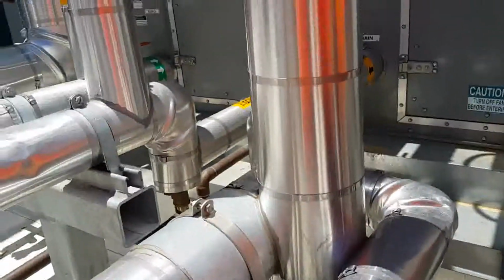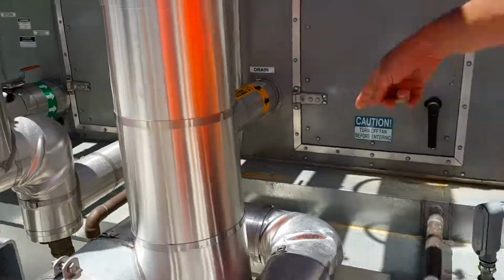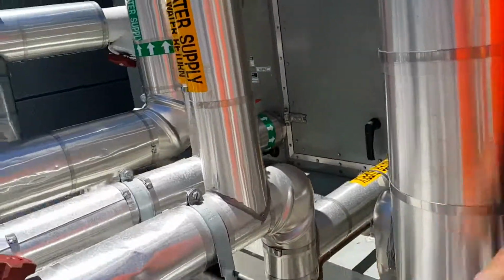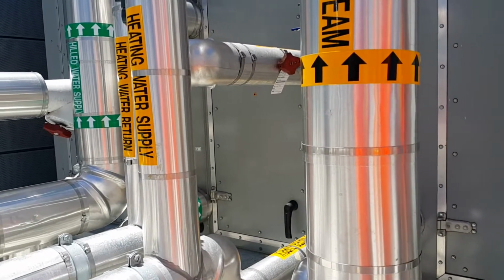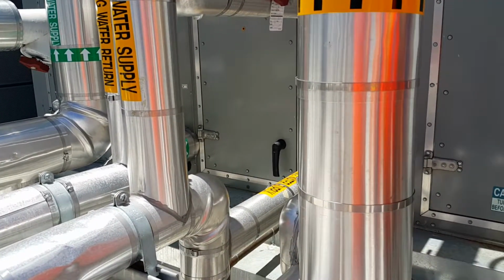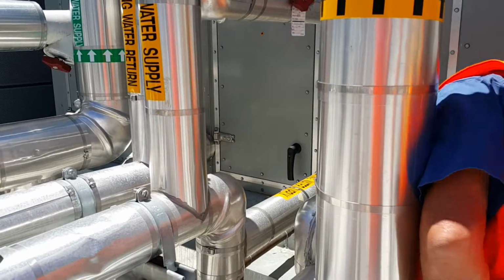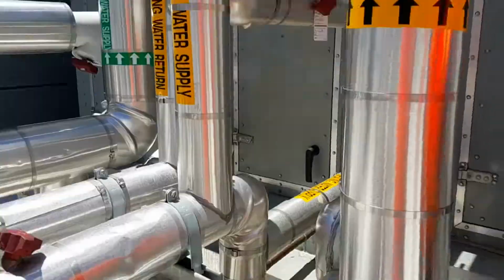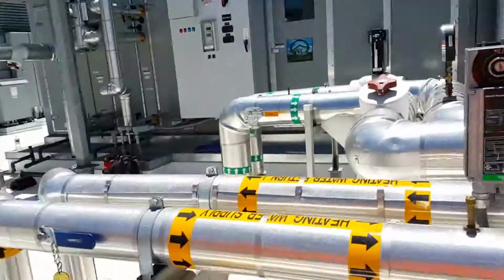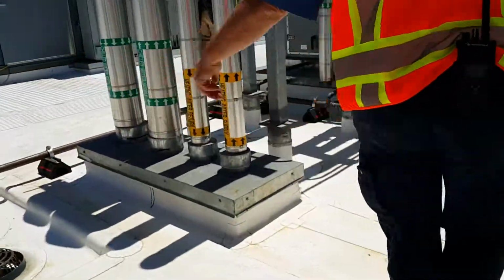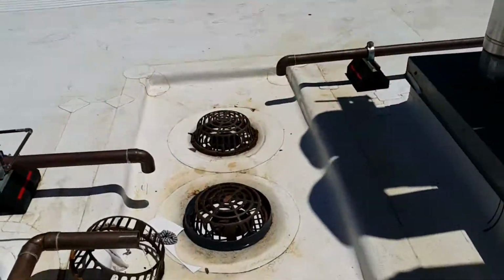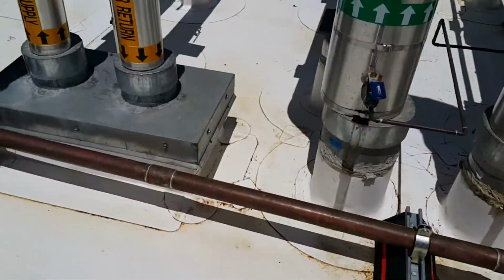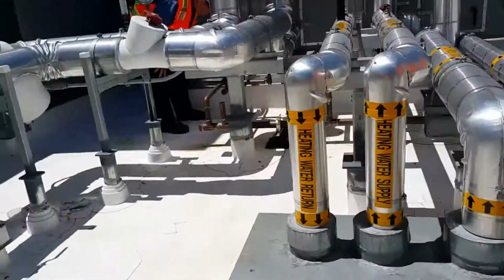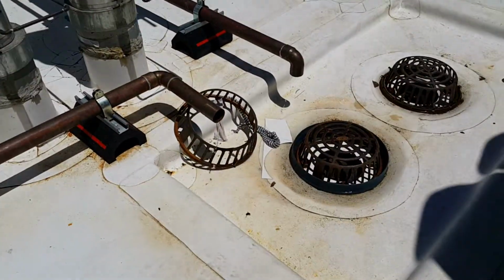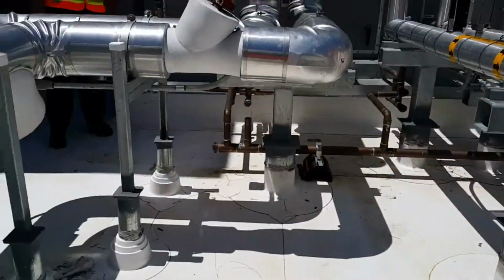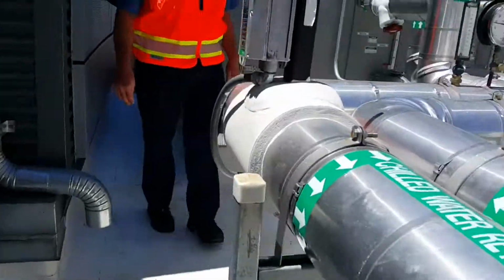This is for the steam. Actually this is probably for the steam, and that one's for the coil. Is that trap with the ball? What's that? No, you see that right here? This is the trap. They might, because we are moving, you see a lot of water coming out of this. We are moving condensate. Put a thing in there, collect a gallon of water in a couple of minutes. Yeah. Nice to see it look right.